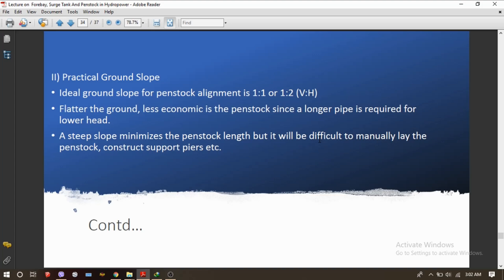On flatter ground, the penstock alignment will be less economical because a longer pipe will be required for a lower head. As we know, lower head produces lower power since power is proportional to head and discharge. A steep slope minimizes the penstock length, but manually laying the penstock pipe on a steep slope is very difficult, and construction of support piers and saddle supports will also be very difficult.